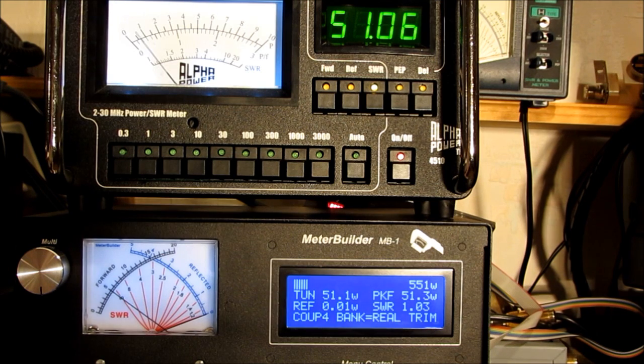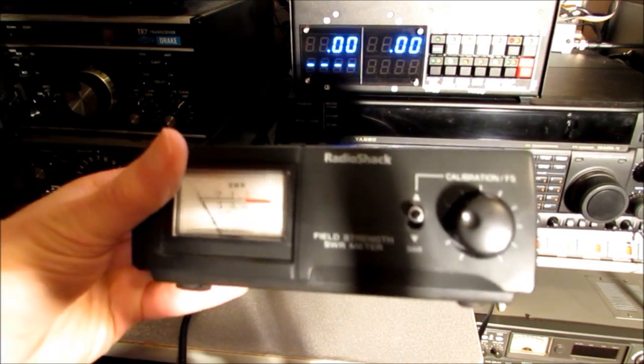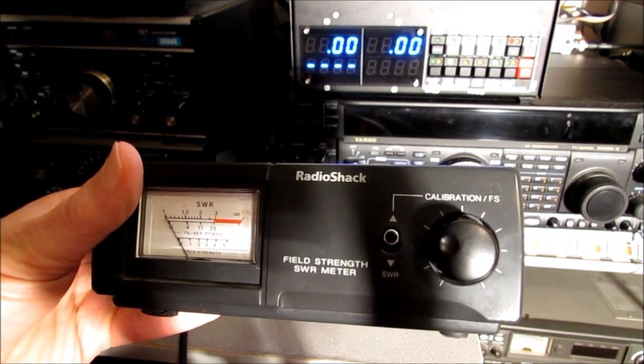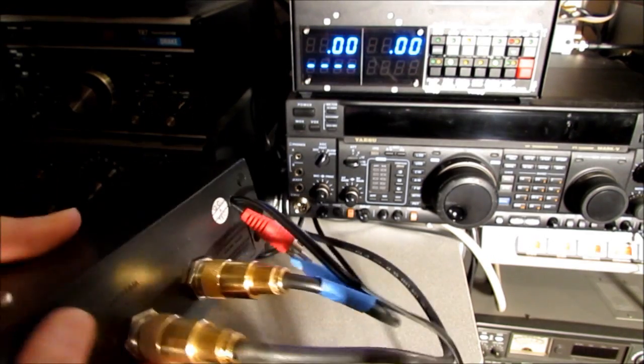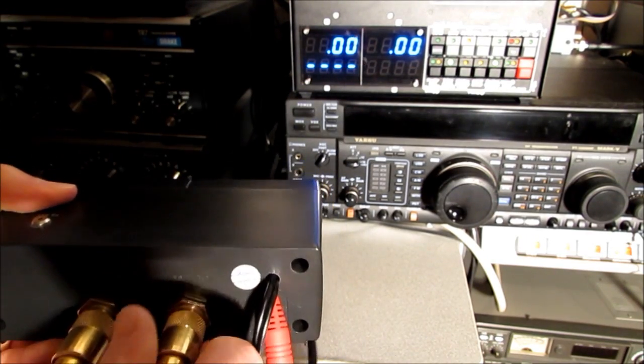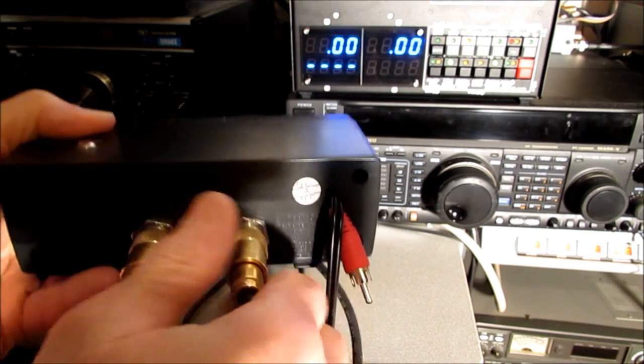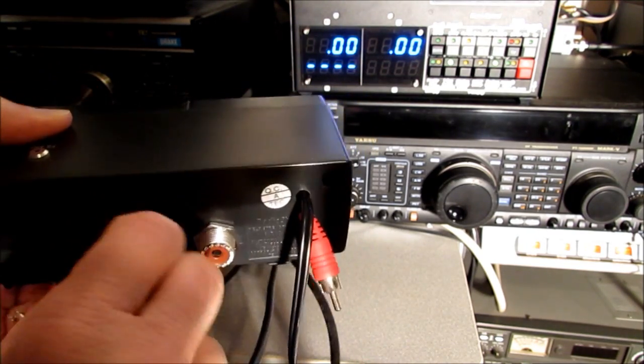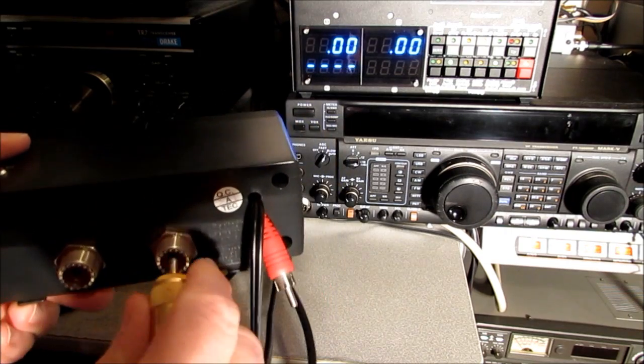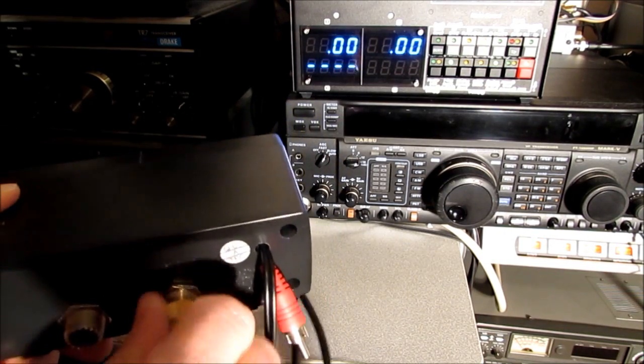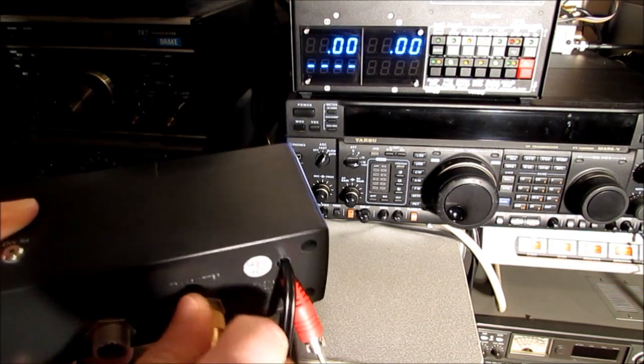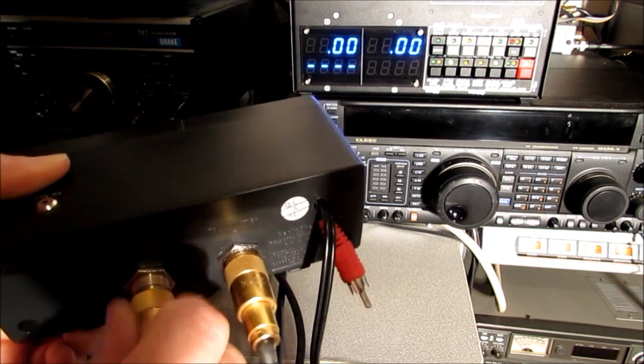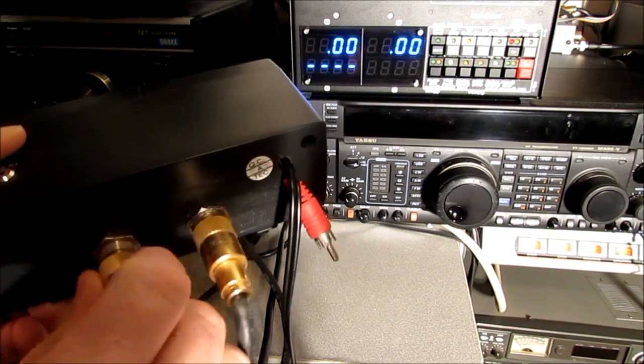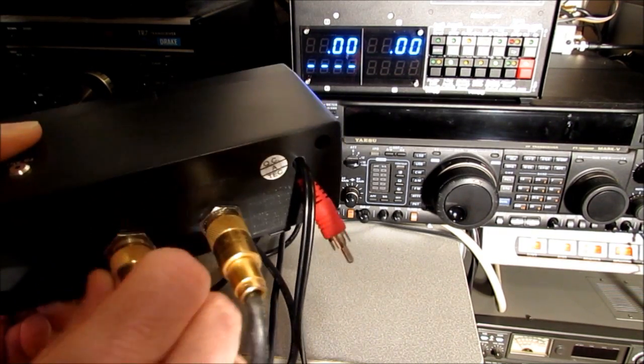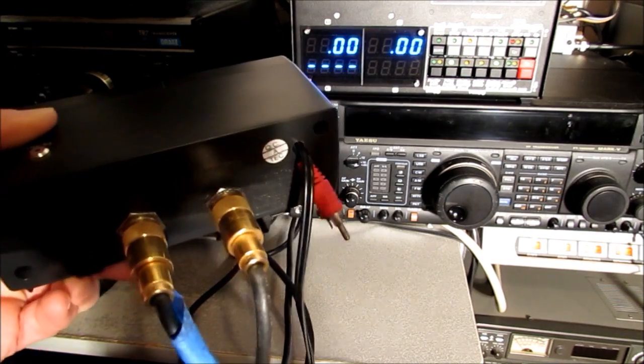So let me show you what we have to do to adjust the reflected channel. Now, to do the reflected channel calibration, I have to swap these two connectors so that the power I'm feeding through the coupler will effectively be read by the reflected channel port. And just don't forget, after the reflected channel calibration, to change these back.